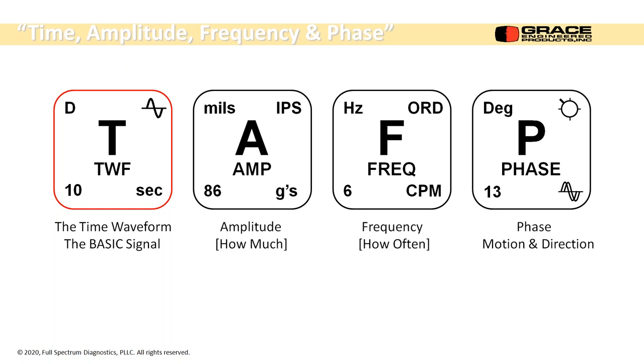All right, now the new stuff. We're going to talk about time, amplitude, frequency, and phase. The key things are amplitude, frequency, and phase. Those are the biggest diagnostic tools. Amplitude is a severity indicator, so it's how much. Okay. Here inside the icon, there's mils, there's inches per second, and there are G's. So this is displacement in thousandths of an inch. This is inches per second. It's velocity. This is acceleration in G's.